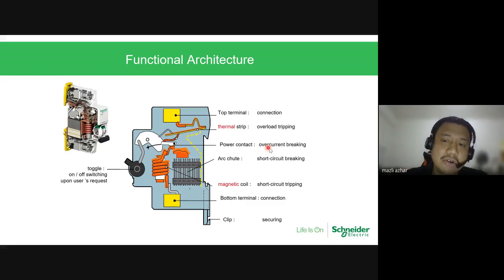We will have a power contact for overcurrent breaking, so for open and close. For arc chute, for everything with electricity, when you force open, you will create an arc. Okay, it will not be as big as the vacuum circuit breaker or air circuit breaker, but the arc that is generated when you open and close the circuit must be extinguished at the arc chute. You will have a magnetic coil for short circuit tripping.